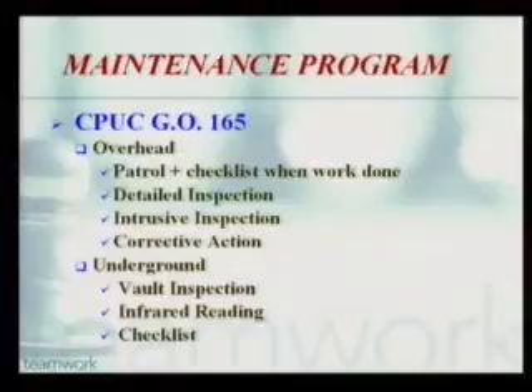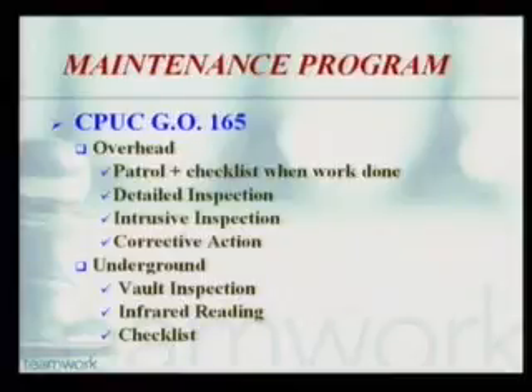Corrective actions are done right away, with one exception: in 2004 we hired a consultant. We have over 15,000 poles, and the consultant came in and inspected every single pole in our system. We found several major and several minor problems. We've fixed all the minor problems, but not all the major ones, because a lot of that will be part of our reconstruction project for 12 kV.